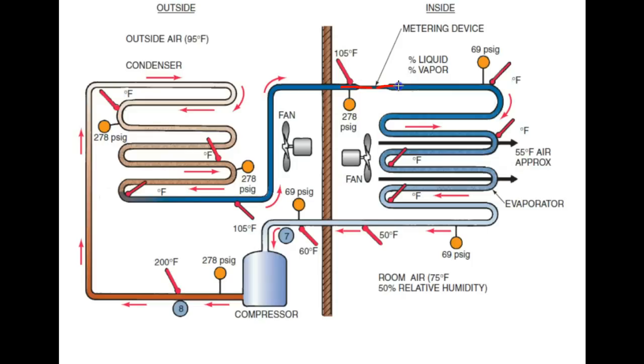And it flashes over into liquid and vapor in the evaporator coil and it's at its saturation point. And these coils are designed so that when the system is operating properly and charged properly, that the refrigerant is at its saturation point through the majority of the coil. And it's designed to do this so that it can pick up the maximum amount of heat it can from the indoor air that's being blown across it by the air handler.